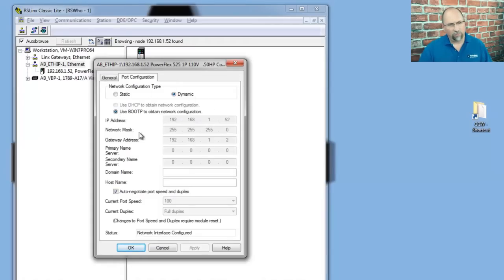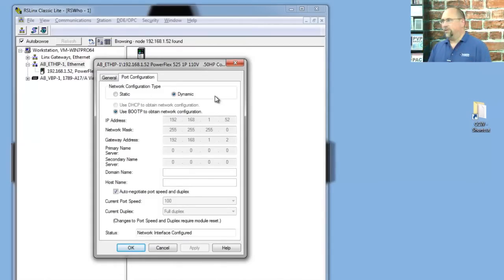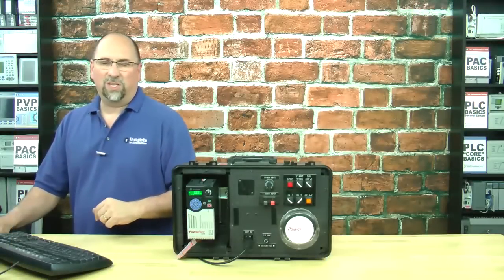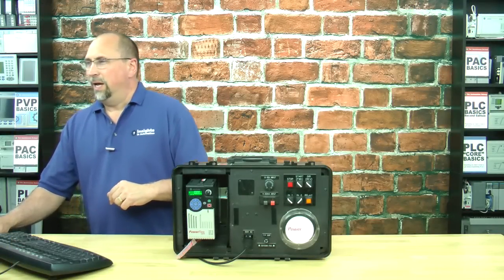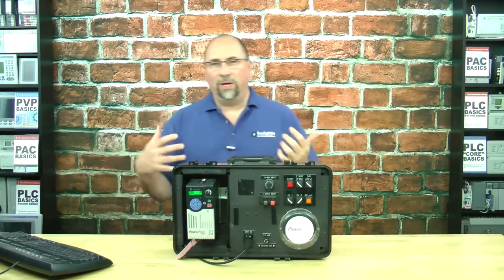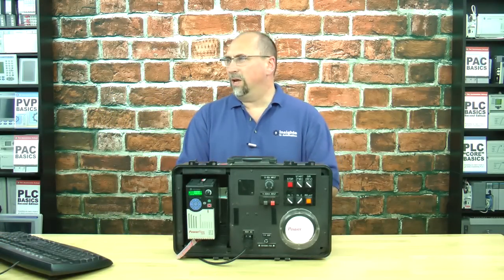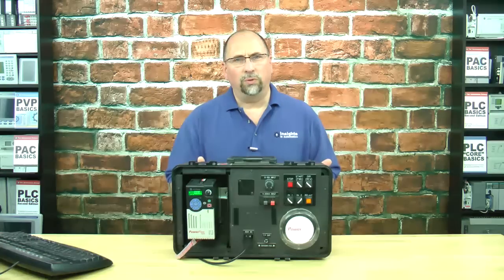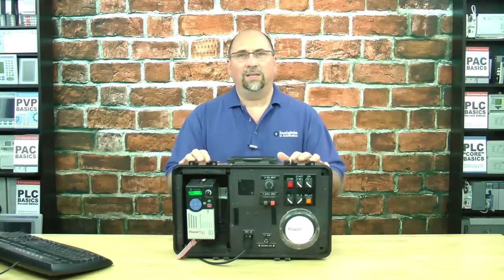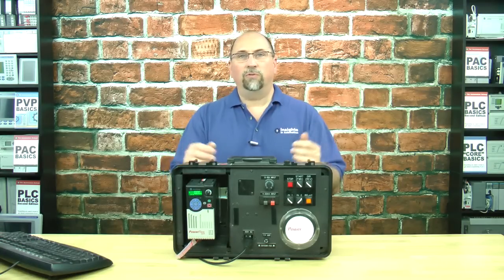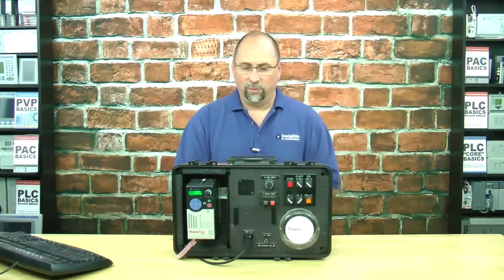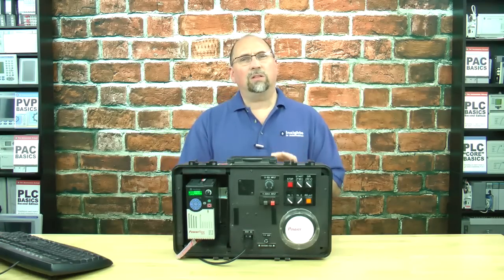Now, from here, it looks like it's still set up for BOOTP, but when I cycle power to the drive, it'll come back up as static. And that's how easy it is to use the BOOTP DHCP tool to set the IP address of your PowerFlex 525.